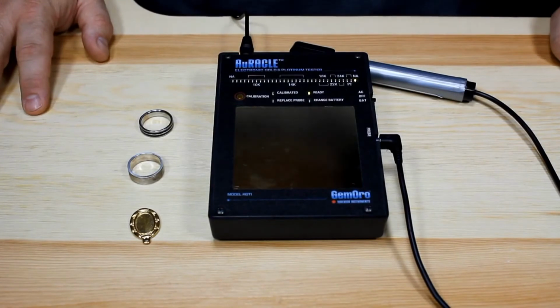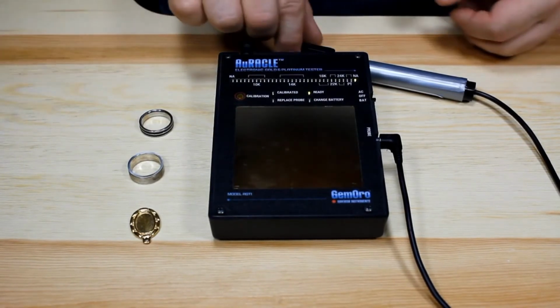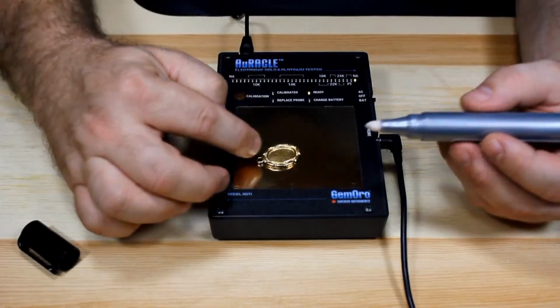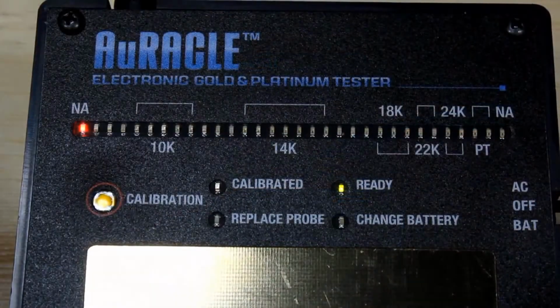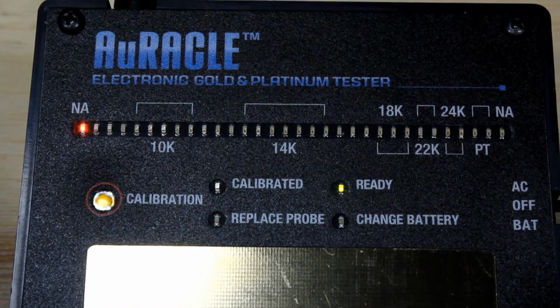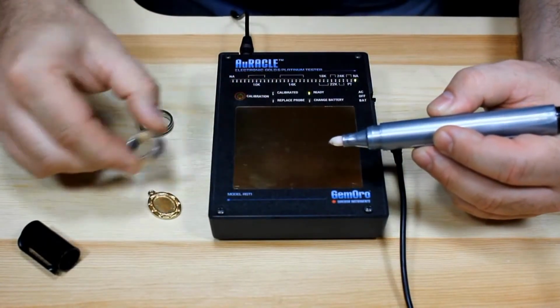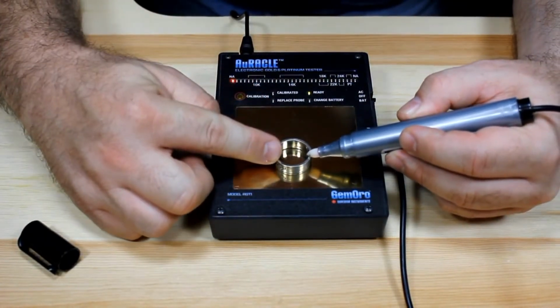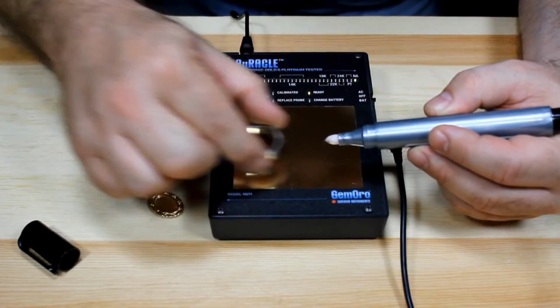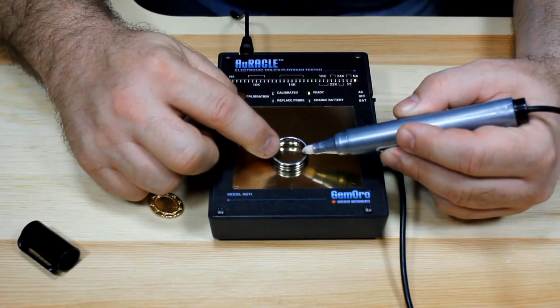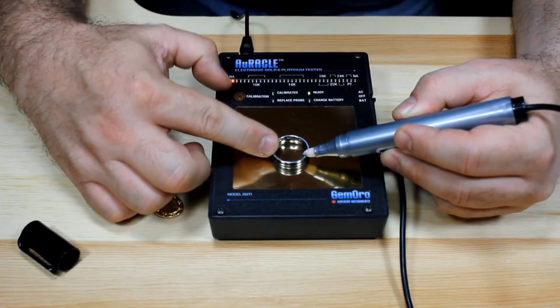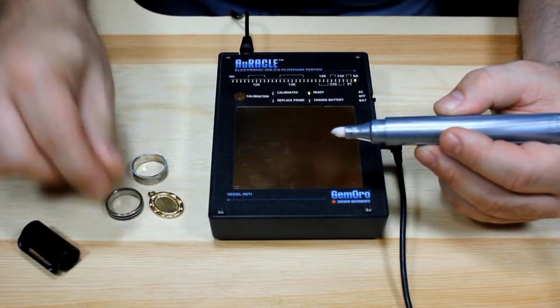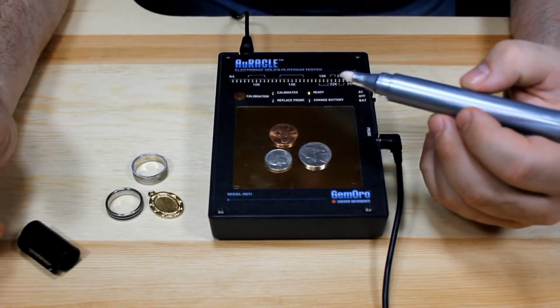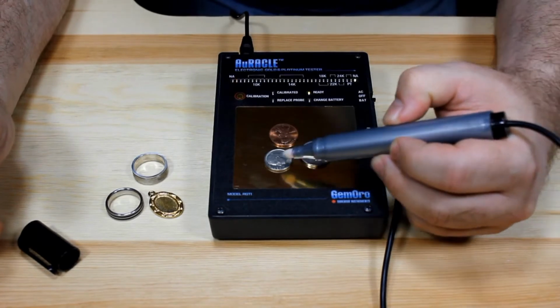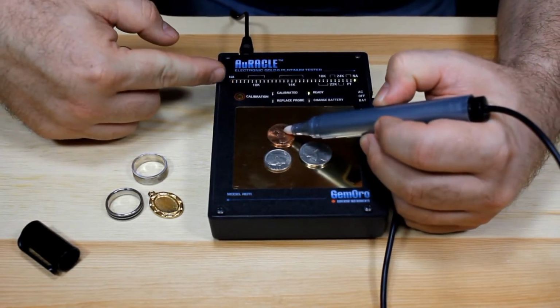Now I'm sure you're curious as to how the machine will react when testing other kinds of metals, so let's find out. I've got a gold-plated piece that when I test lights up red, N/A, letting us know definitely that is not a gold item. Got a silver ring. How will that react? Again, same thing. It's not gold. And I've got a stainless steel ring as well. No, went all the way down into the N/A range. That was not gold either. In fact, any base metal item, when tested on the machine, will always come up as not gold.